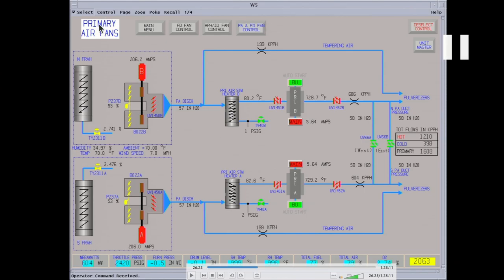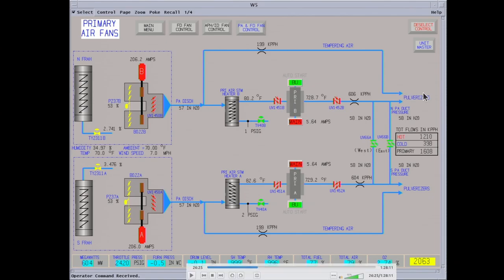This is the fan room. These are the primary air fans — 3,500 horsepower motors. Right now they're putting out 57 inches H₂O. This feeds your pulverizers. Part of the air is bypassed to the air preheater; this is tempering air. You want your coal at around 140 degrees coming out of the pulverizer. Right now it's about 728 degrees coming out of the air preheater. There are two air preheaters — one feeds the north and one feeds the south. The purpose is to transport the coal into the boiler and provide part of the combustion air.